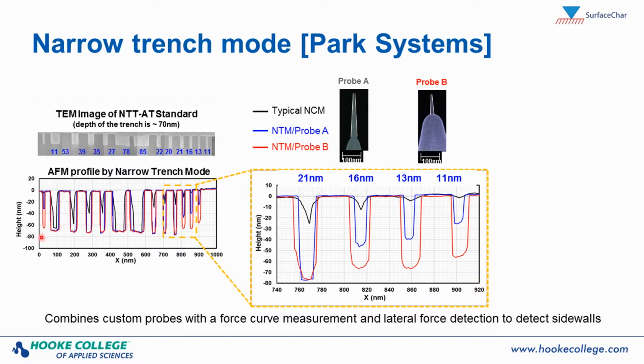And this black profile is the profile of what a standard mode AFM can do, where you can see that the trenches that are especially deep and narrow, the AFM tip simply can't get in there to get an accurate measure either of the width or the depth of the trench. And so what they've done in this narrow trench mode is an interesting technique where they do what are called force curves or single point measurements, where the probe, it's not imaging, it's just coming in and out at every point. And then they've added a lateral force detection on the side-to-side motion, so that there's a very easy detection of where these sidewalls are, so that the tip knows where the sidewalls are.